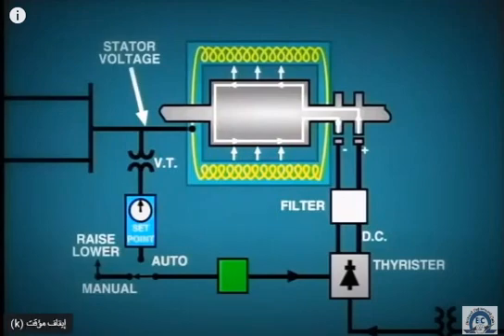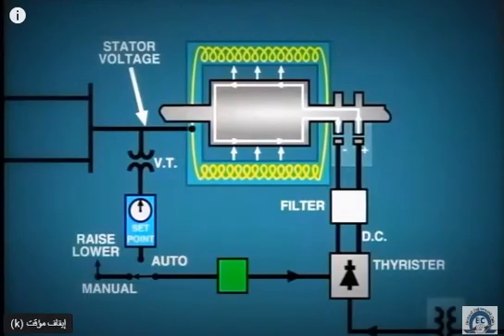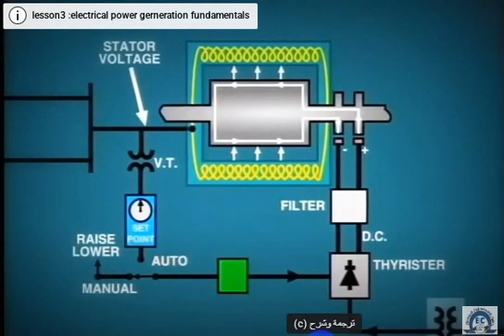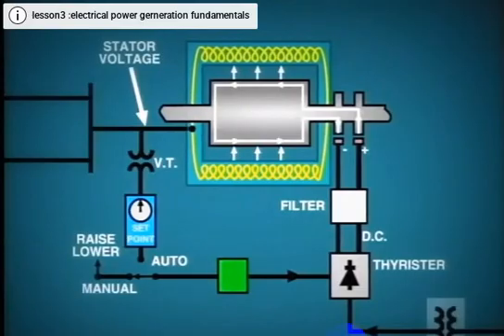The DC current from the rectifier is supplied to the rotor winding through collector rings on the shaft. The incoming AC to the rectifier is supplied from a dedicated transformer. The primary side of this transformer is fed from an auxiliary bus, or in some cases, the generator bus itself.